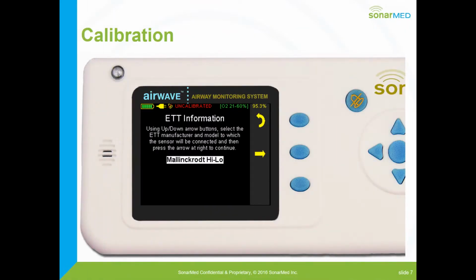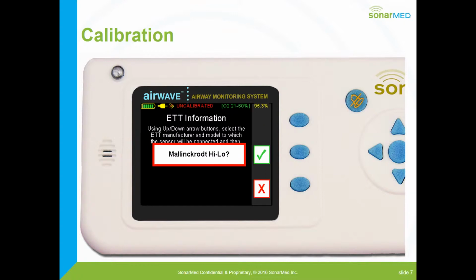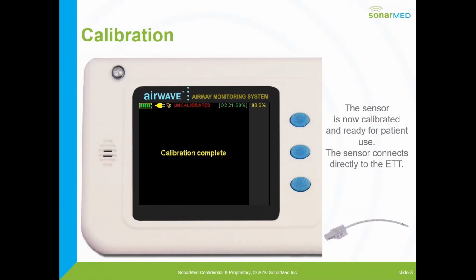A very quick calibration. Next, I'm going to see a screen that asks me what type of endotracheal tubes I have. Mostly you're going to see a Mallinckrodt. That's what the large part of the market share is. But there are others loaded as well, and you're going to use your up and down arrows to find your type of endotracheal tube. When in doubt, simply select Mallinckrodt. Once you've selected it, it asks you to confirm it. Message: the calibration is complete. And now it's ready, and you're going to connect the sensor directly to the endotracheal tube.